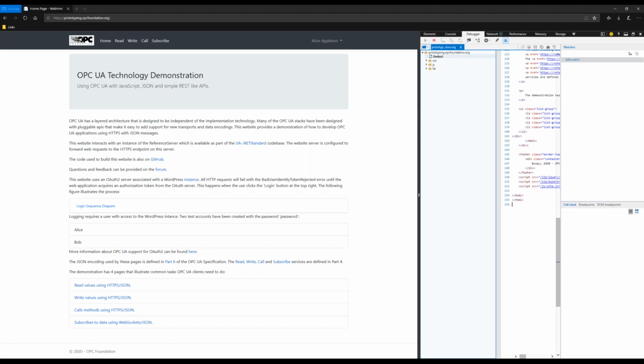I think we need to mention that this mechanism only works for recent OPC UA servers that support JSON encoding and transport, and not legacy old versions. Any solution for legacy devices? Yes, that is correct. Obviously this will only work if you're talking to a server that supports the new protocols. However, with OPC UA, you have a number of options available, in particular aggregating servers, where you have multiple servers chained together. So you could have a new server acting as a gateway that supports the protocol and simply passes the request through to a downstream server that only supports UA TCP.